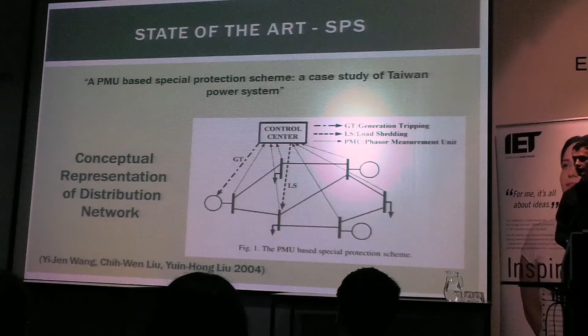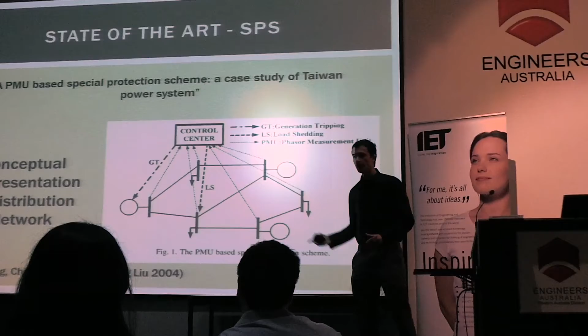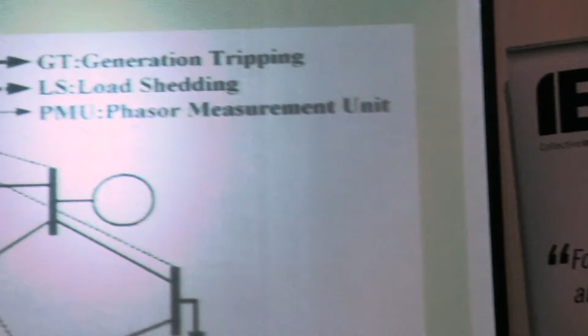This schematic is a general representation of a distribution network. The circles are generators, the vertical lines are bus bars, and the other lines are distribution lines. This rectangle here, the control centre, is the guts of the SPS. We can see that the data from each of the generators and bus bars is being sent to this control centre, and thereafter the reliability algorithms determine the remedial action.